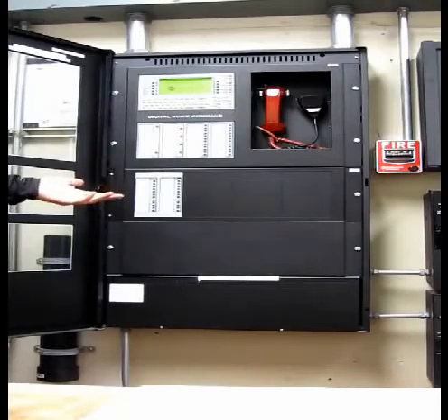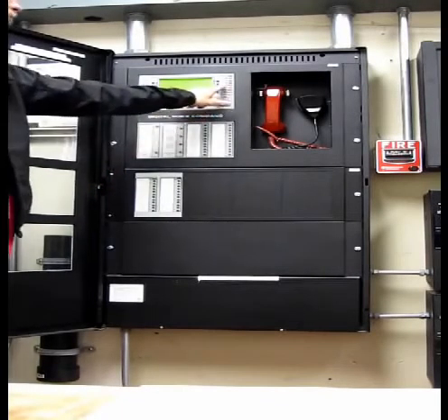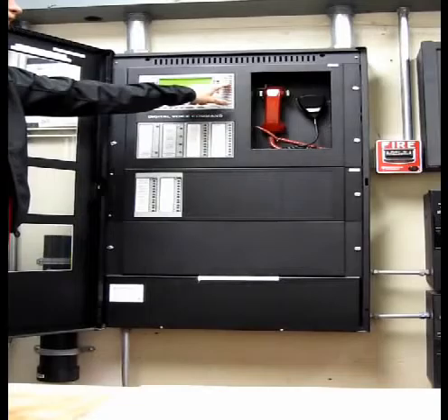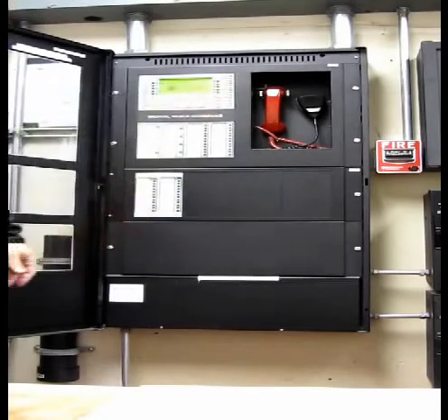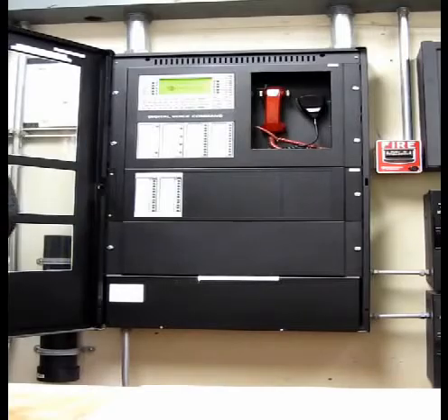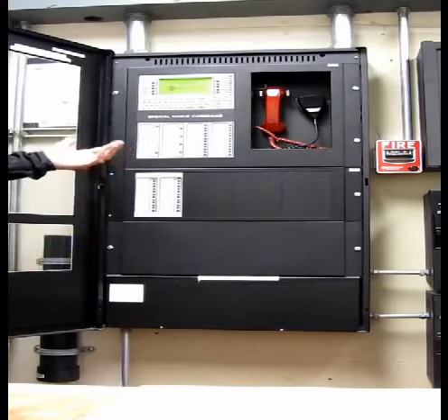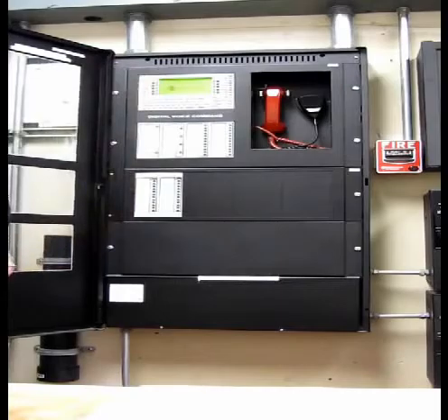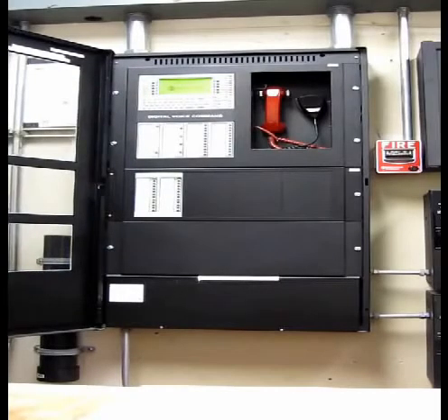Now if you guys are ever required to do a fire drill from the fire department, which I doubt because we're going to be doing annual testing for you, just in case you want to know, there's a drill button right here. If you hold that button down for 2 seconds, it'll activate all of the silenceable signals in the building. So just be careful with that one. Don't hold it down. That's why they make it for 2 seconds. It's kind of hard to mistake a button and hold it for 2 seconds.